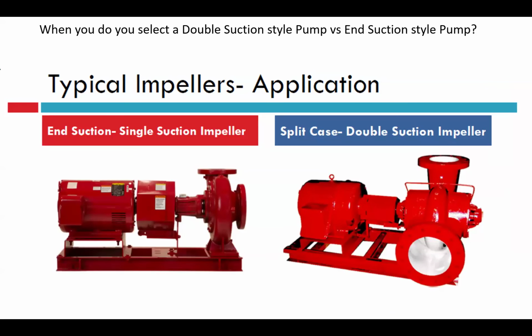Sometimes a question will come up, hey, when do I make that decision? When do I go from one to the other? When do I go from end suction, single suction impeller to a split case double? And it's not written in stone, but kind of a rule of thumb that the industry's accepted. It's typically flow rates as you start moving up over that 1,500, 2,000 gallon a minute, you're probably going to move into this split case double suction versus the end suction.